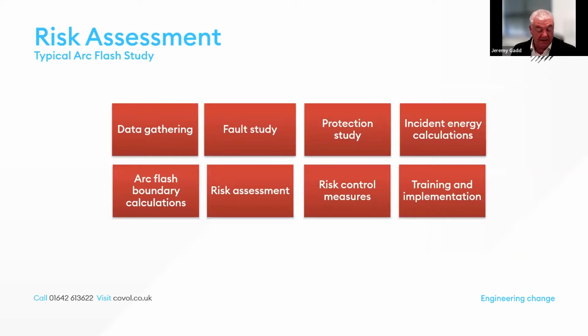So a typical arc flash study consists of a number of different sections, and each one plays a separate part in compiling the end result. Everything from data gathering through to conducting the fault study, determining what the boundary calculations are, doing the risk assessment, and then looking at what risk control measures can be put in place, whether or not a protection study is needed, and then if necessary, training and implementation. The output of the exercise is a report detailing the worst case findings. Because obviously with this, it's always about the worst case. It's the if question all the time with arc flash. If it does happen, this is what is likely to happen. It is a risk assessment.